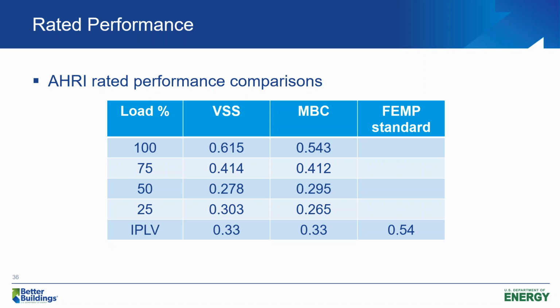The IPLV is identical for both chillers, and it's significantly lower than the FEMP standard for chillers. So there's about a 35% improvement over the FEMP. FEMP is the Federal Energy Management Program standard for chillers. And that's already a good chiller, so these are both very high performance chillers.